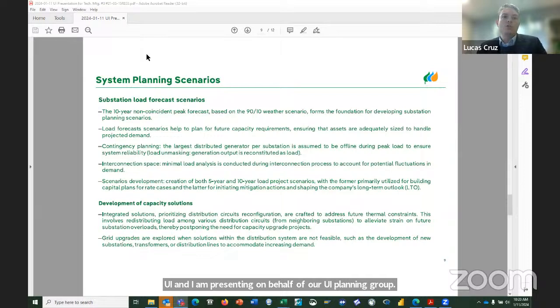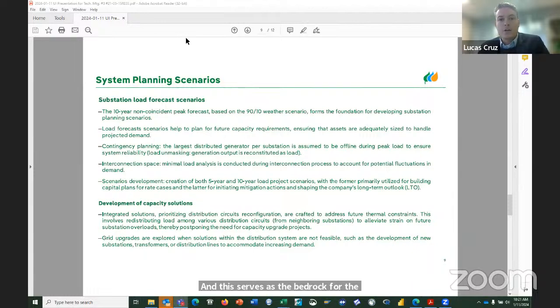Moving to system planning scenarios: here we develop substation planning scenarios on an annual basis. Every year we receive the corporate level forecast developed by my colleague Mike, and then we use this system level forecast to develop our system planning scenarios. We start working with the 10-year non-coincident peak forecast, based on the 90-10 weather scenario that Mike explained, and this serves as the bedrock for substation planning. This forecast not only anticipates future loads based on extreme weather conditions, but also serves as the basis for sizing assets properly to meet the projected demand.